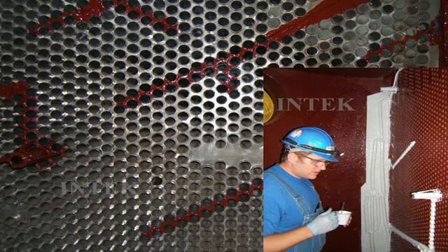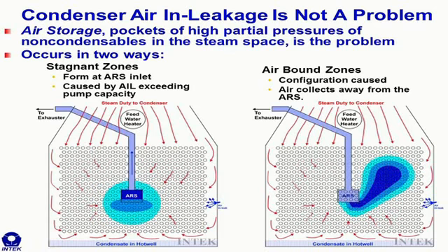Over on the right, you can see a side view of the instruments installed in another condenser and the flow and fouling meter. So the data from these instruments are used to create those performance profiles that I showed on the second slide and I'll show later on. But before I show some performance profiles of different condensers, it's important to understand how air affects condenser performance. The title of this slide is Condenser Air in Leakage is Not a Problem. And I'll say that again just to let it sink in. Condenser air in leakage is not a problem. That title is meant to be provocative and challenge all of your thoughts on how air in leakage affects condensers.